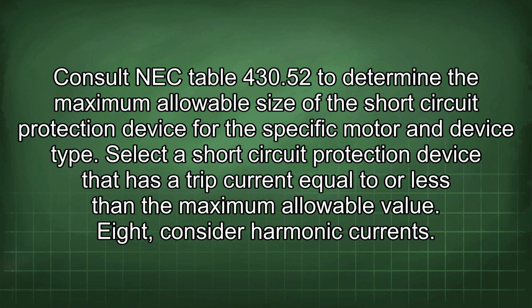Consult NEC Table 430.52 to determine the maximum allowable size of the short circuit protection device for the specific motor and device type. Select a short circuit protection device that has a trip current equal to or less than the maximum allowable value. Eighth, consider harmonic currents.